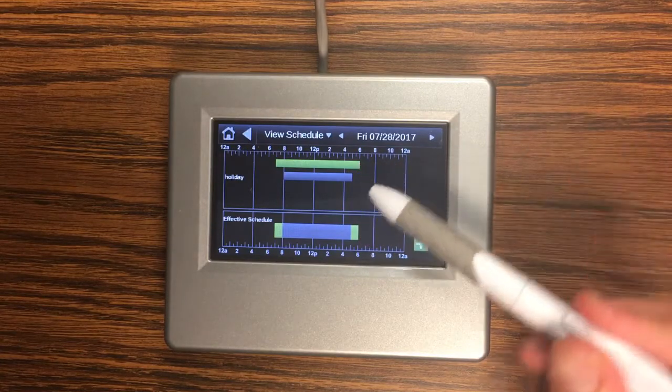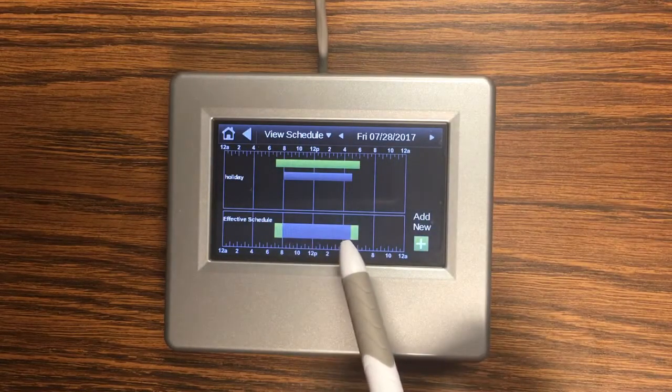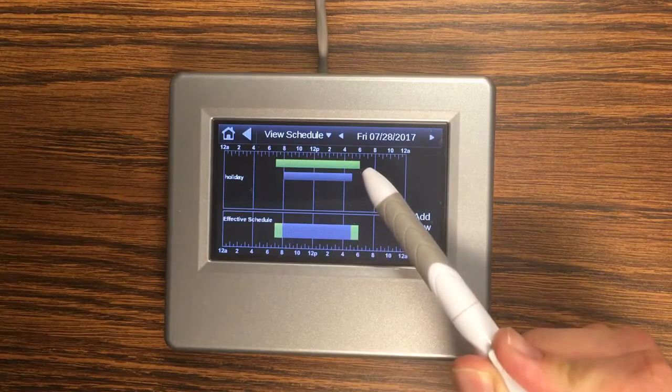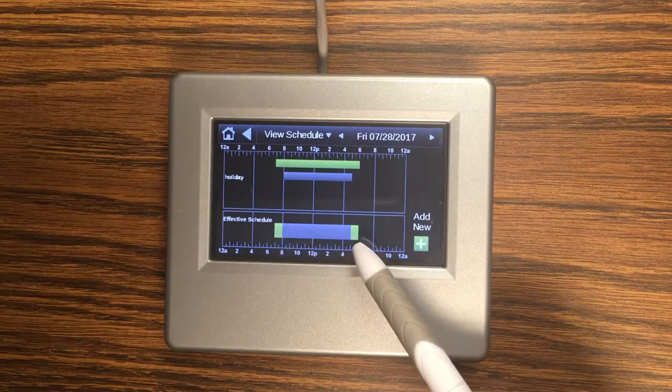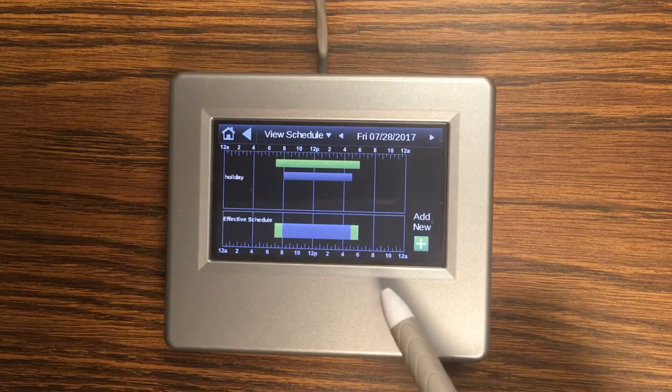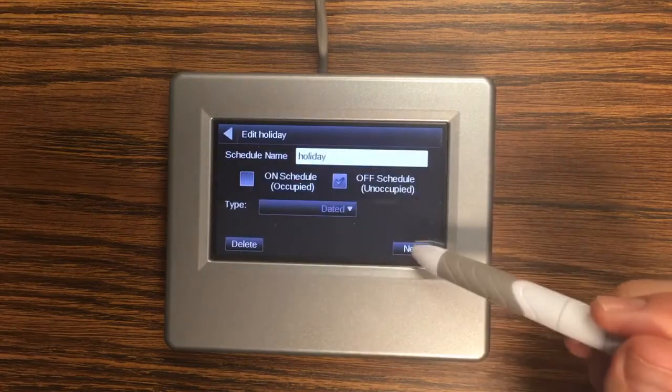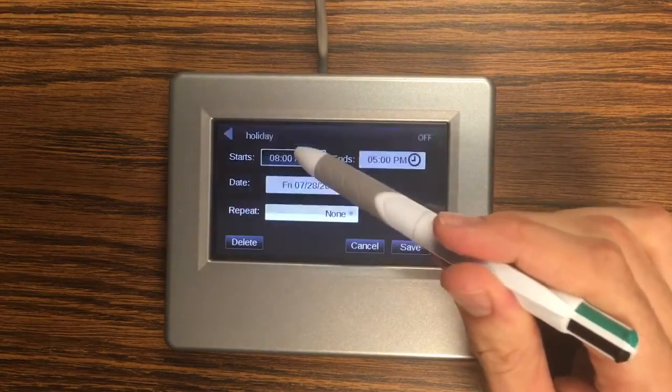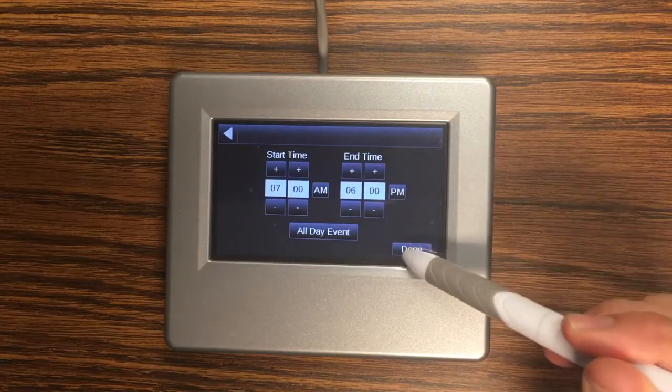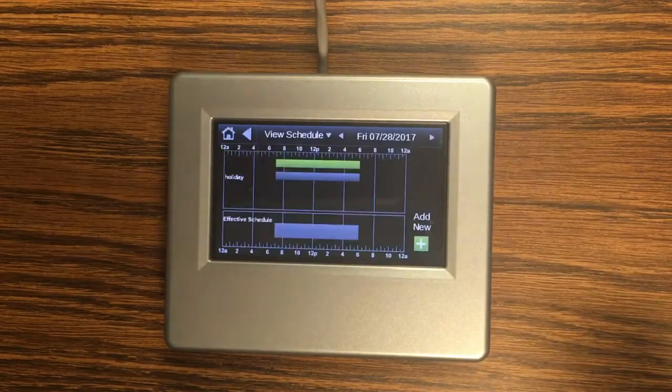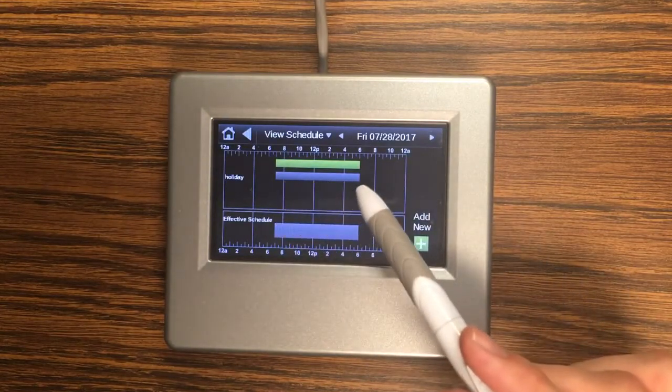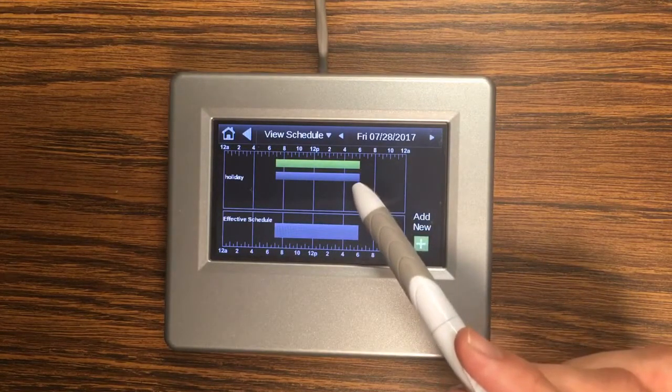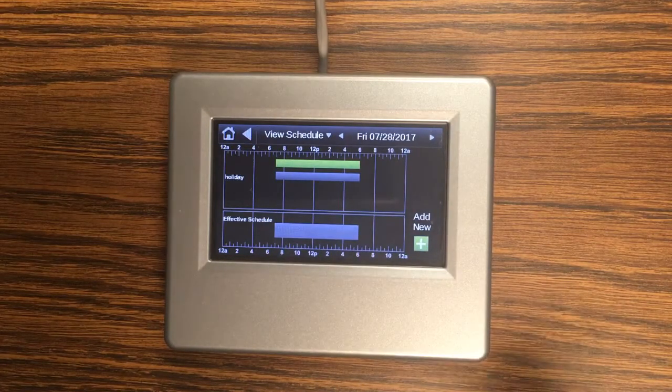And you can see I didn't do this quite right because my holiday schedule is from 8 to 5 whereas my normal occupied schedule is from 7 until 6. So I have these little occupied ends on this schedule which I don't want. So in order to fix that simply click on the schedule that you want to edit and change the values. Now you can see I've effectively cancelled out the normal occupied period with this holiday schedule resulting in an unoccupied effective schedule.